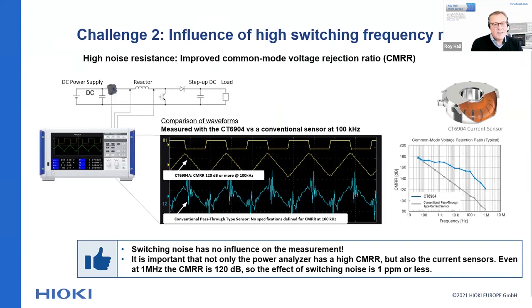The second challenge that the increase of frequency has created is the influence of high switching frequency noise. To explain this phenomenon, I'd like to go back to the reactor loss measurement. On this slide, you see a typical circuit to measure the reactor loss of a device, where you can see here a current sensor and the voltage measurement. When we look here at the center of the slide, we see a screenshot of the instrument, and at the top we see a switching voltage, a square voltage, with a frequency of 100 kilohertz. And that frequency is realized by switching this semiconductor hard.